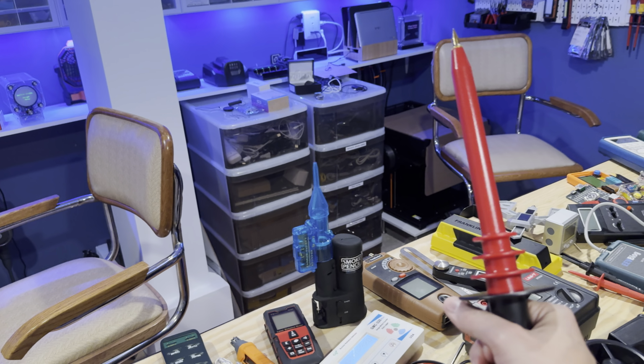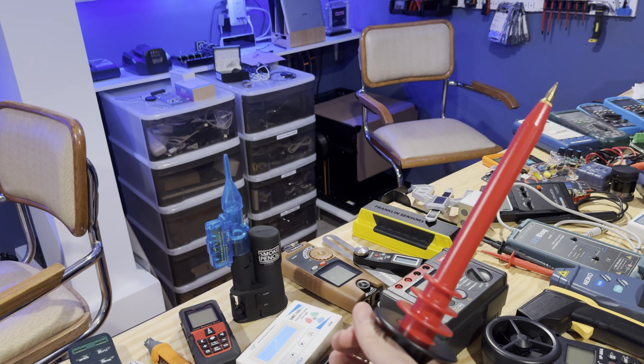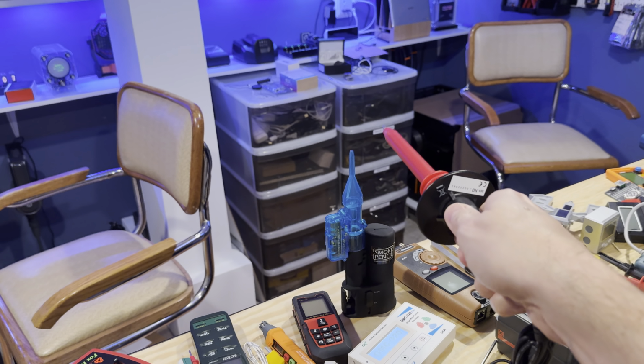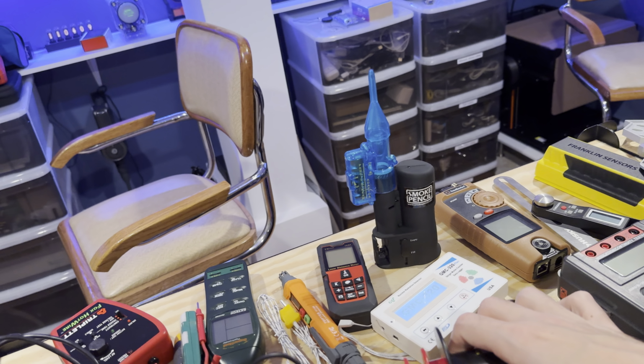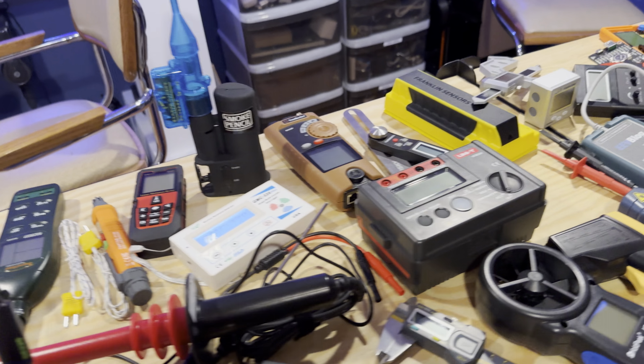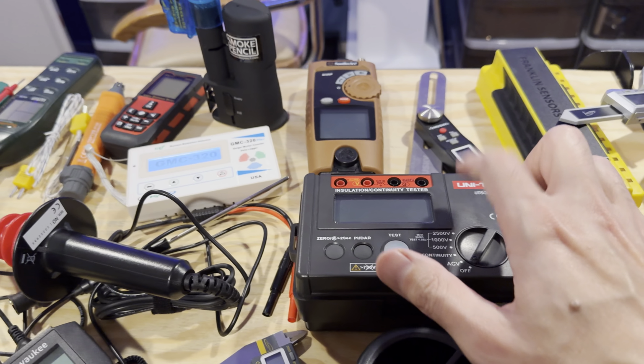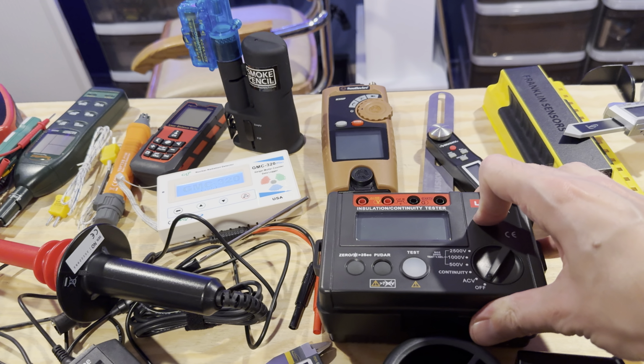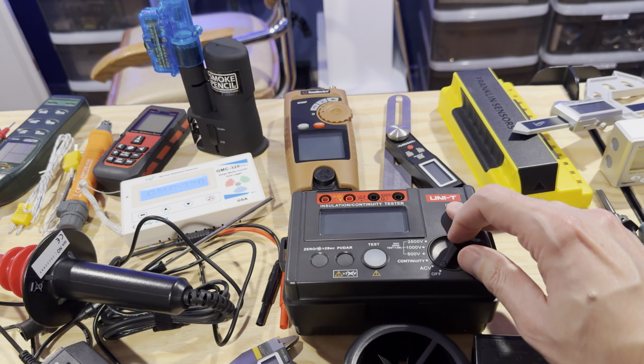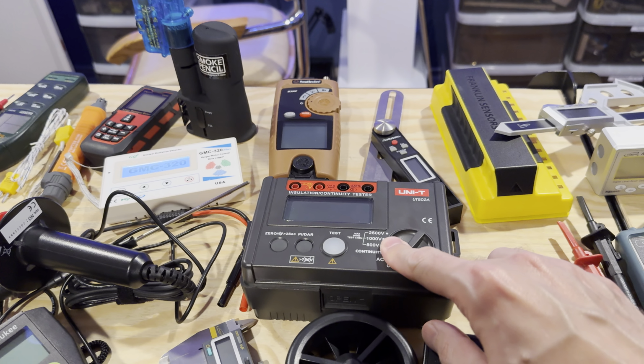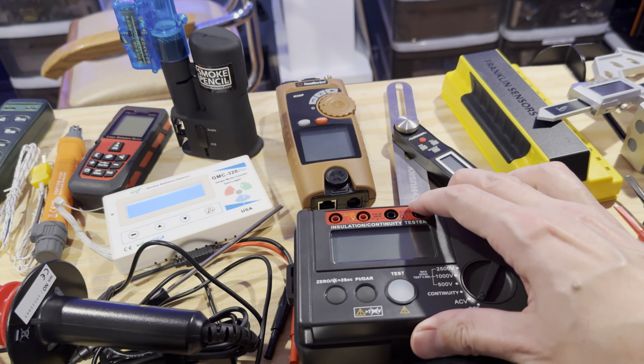This suspicious looking device here is a 40,000 volt probe that allows you to measure high voltage things without getting too close and touching them. This tests the insulation of wires by putting up to 2,500 volts through them and measuring how much the resistance breaks down.